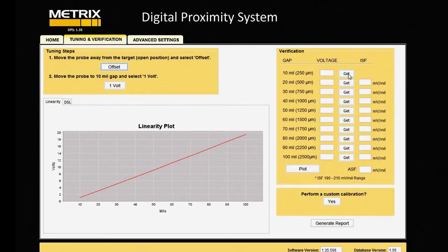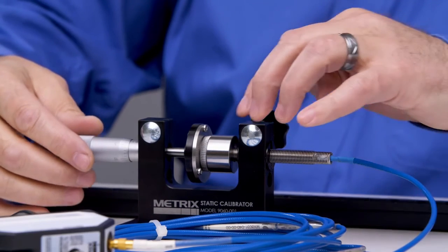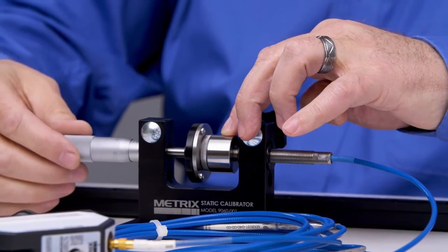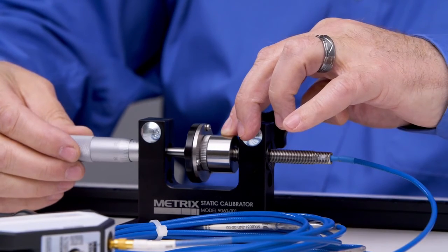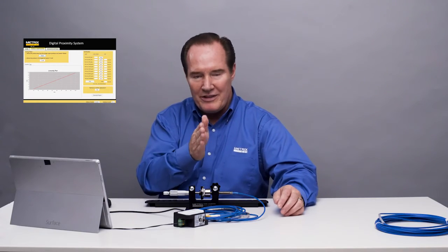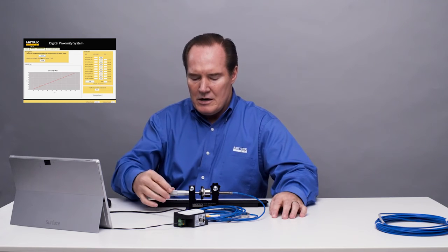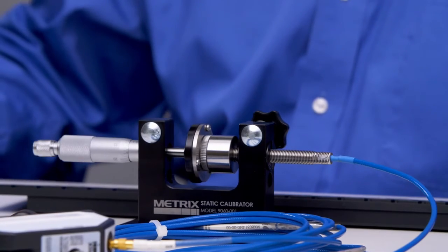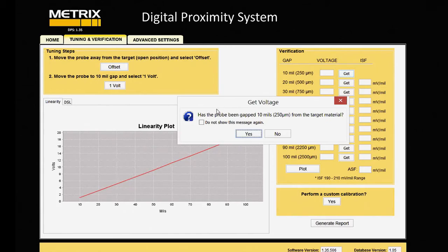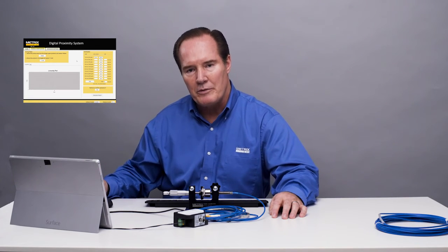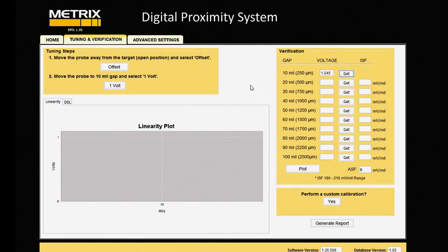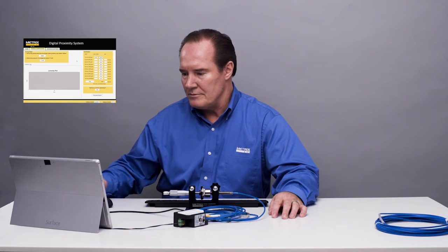The first thing we're going to do is move our micrometer out to 10 mils. And I hold the fixture steady so that it doesn't move. I want to keep it parallel with the probe tip so that they stay in a nice straight line. So I'm at 10, and I'll say get. It gives me the warning. I'll go ahead and turn that off. It gives you that warning each time. I know I have to move the fixture before I hit get. So just remember that when you're doing this yourself. And I move this in 10 mil increments, and when we're done, we'll look at our results.